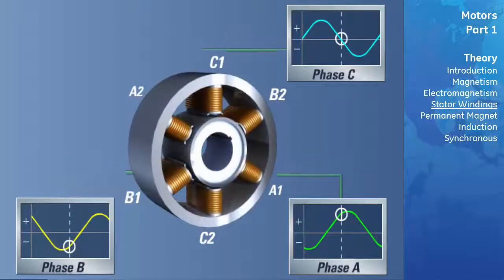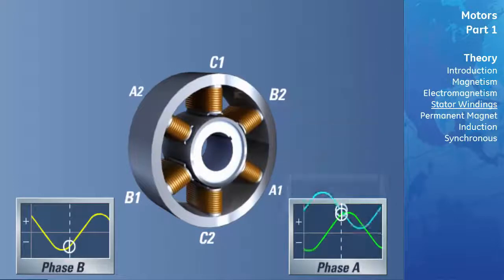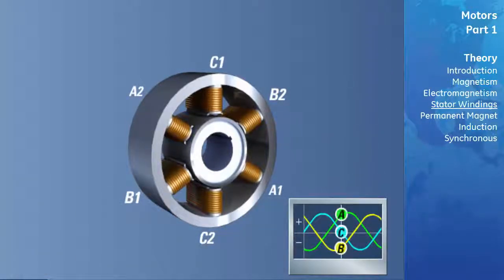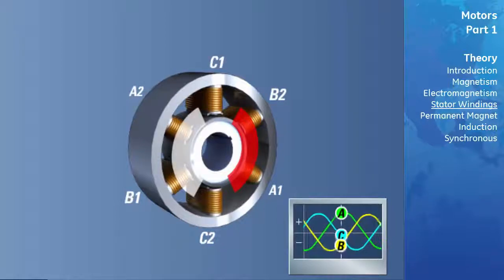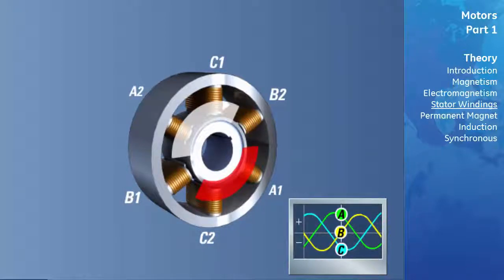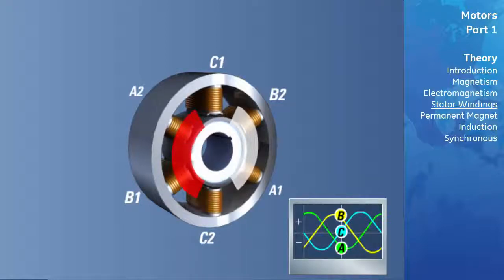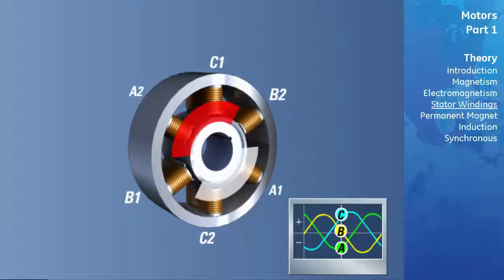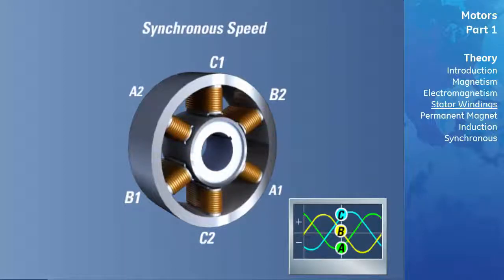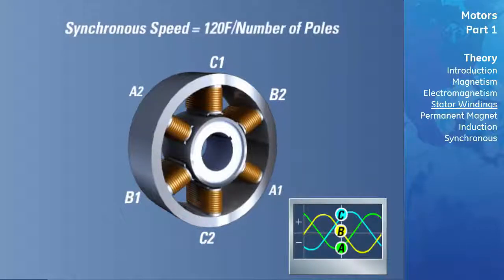If this evaluation is repeated every 60 degrees for the rest of phase A's cycle, we will see that the resultant stator field goes through one complete revolution, or 360 degrees. With a frequency of 60 hertz, this means in one second the field will go through 60 complete rotations, and in one minute, 3600 rotations. The speed of the rotating magnetic field is referred to as the synchronous speed. Synchronous speed can be calculated by the formula: synchronous speed equals 120 times the applied frequency, divided by the number of poles. Applying this equation to a four-pole motor, the synchronous speed is 1800 RPM.